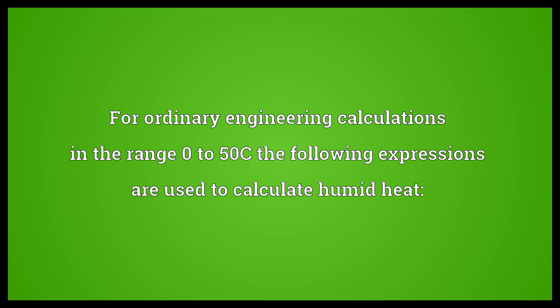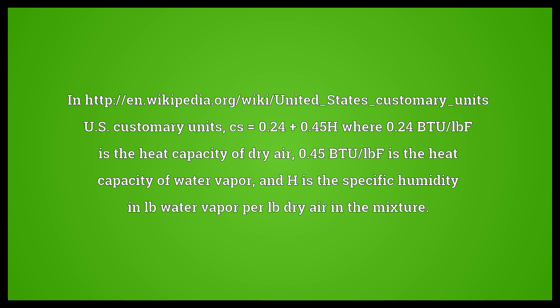For ordinary engineering calculations in the range 0 to 50°C, the following expressions are used to calculate humid heat. In U.S. customary units: Cs = 0.24 + 0.45H, where 0.24 BTU/lb°F is the heat capacity of dry air.